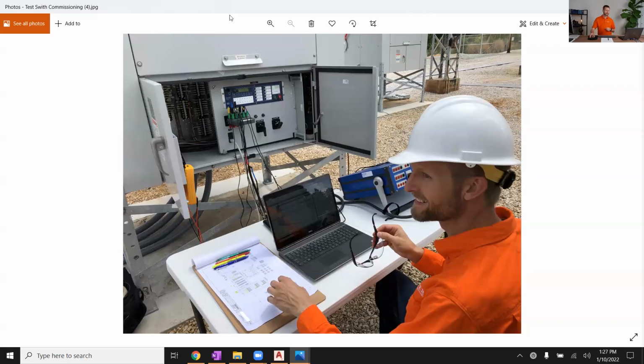But I want you to be aware that the trip signal going out is another great example of a DC signal you would want to have on a test switch. So you can open it up so that as you're testing your relay, you don't accidentally send a real trip signal out to your real breaker to isolate a primary system if it's still left in service during that testing. Hopefully you have a primary and backup relay. You still have protection on that circuit during that situation.